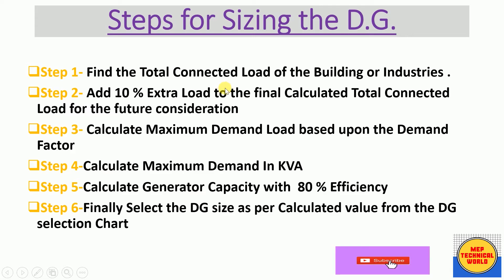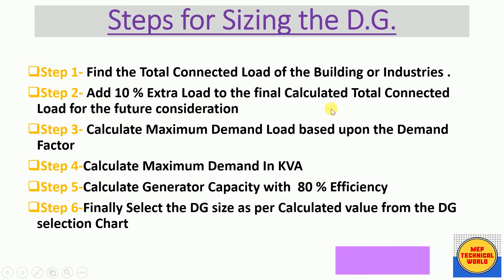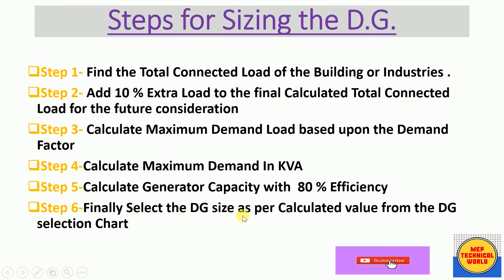We have some steps for sizing the diesel generator. Step 1: find the total connected load of the building or industry. Step 2: add 10% extra load to the final calculated total connected load for future consideration. Step 3: calculate maximum demand load based upon the demand factor. Step 4: calculate maximum demand in kVA. Step 5: calculate generator capacity with 80% efficiency. Step 6: select the DG size as per the calculated value from the DG selection chart. Now let's discuss each step one by one.